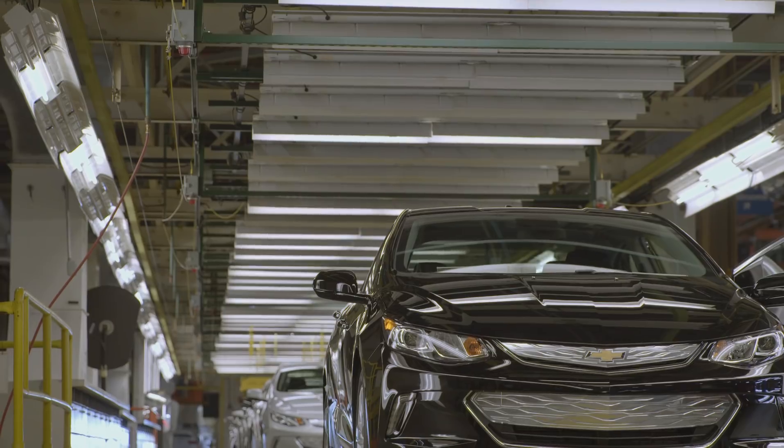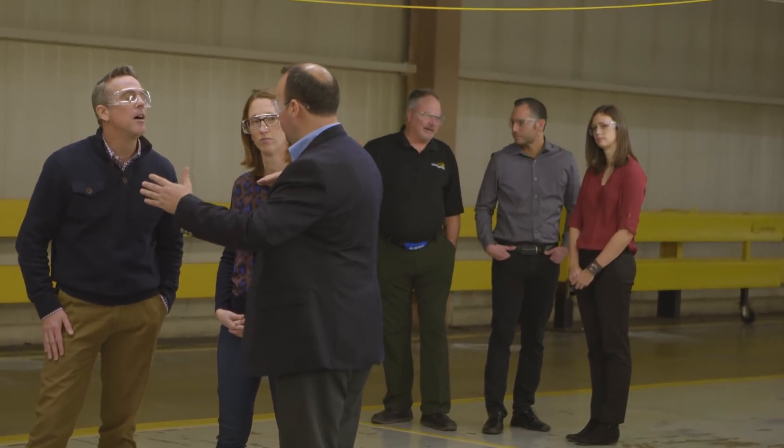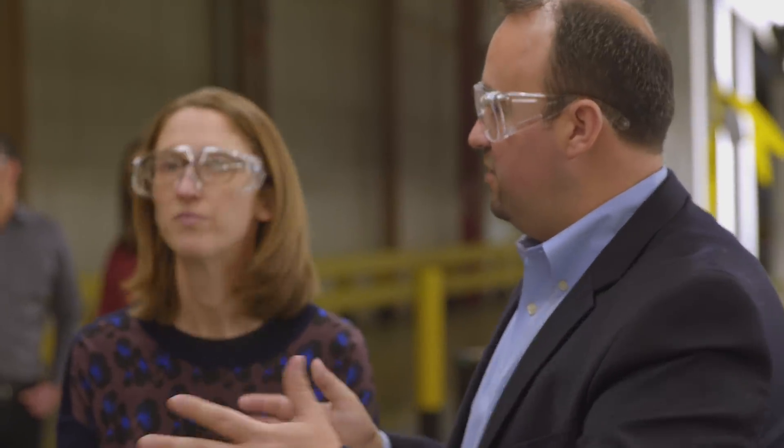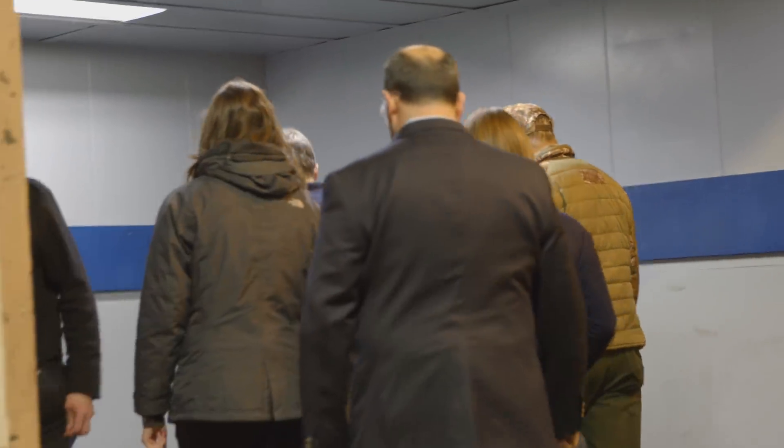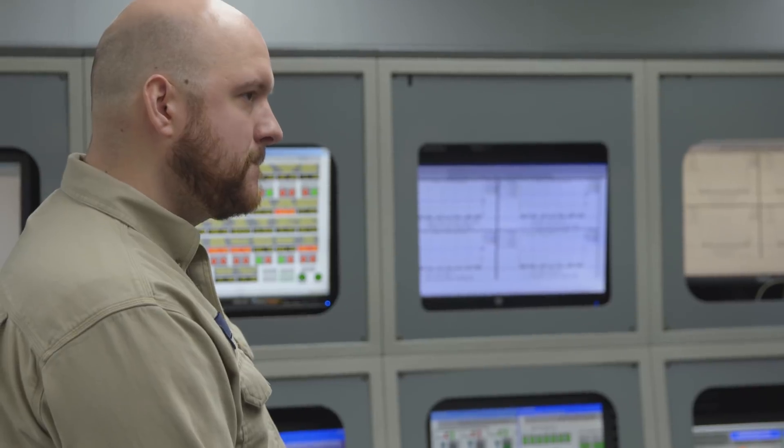It looks like this is where the cars come off the line. I've been noticing there's a ton of fluorescent lighting around — maybe they don't need all this lighting on, or if they need it, they can probably find a better way to turn it on when they need it. Also, they have to open that door to let the cars off the line and outside. It's been good to see that when the car approaches it opens and then closes pretty quickly afterwards, so they don't let that much air in and out. I'm wondering if they can have a trap — as in our plants, in order to maintain stability of the air, we have two air curtains or double doors. You move the car into a door and then close this one so you maintain air there.